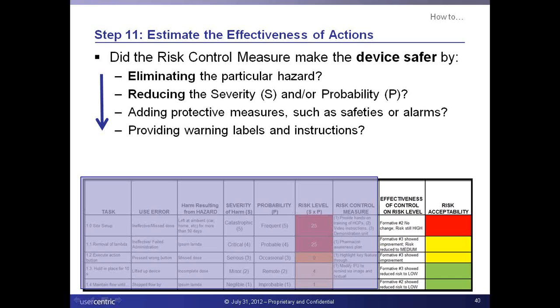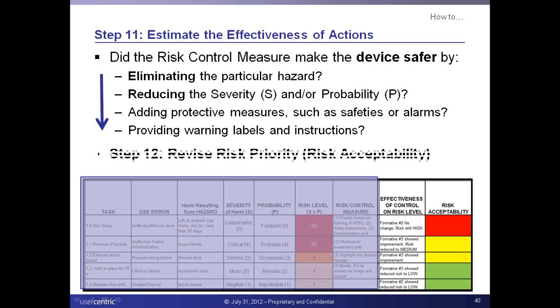There are other ways to make the device safer, where a person has to actually take a positive action to remove something, so you at least have a bit more of a semblance that something was looked at. Or better yet, create a design that already has the risk control mechanism inherent inside it so users can't make that error, which ultimately creates a risk priority and your risk acceptability that will be looked at by regulators in your 510K.